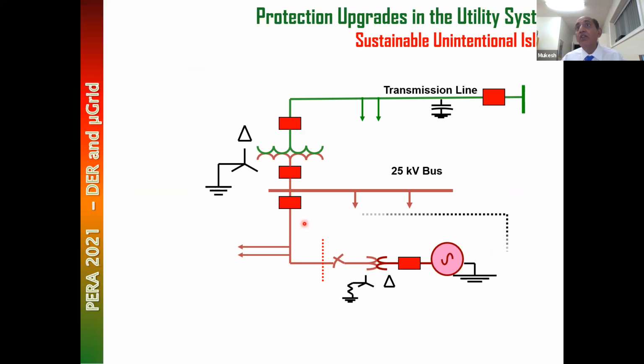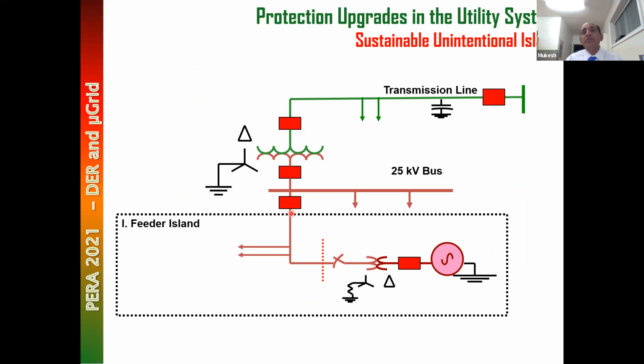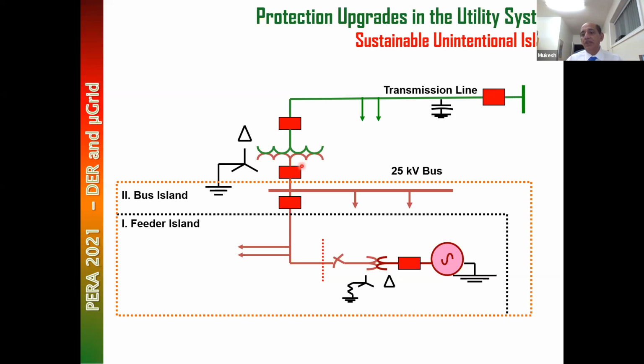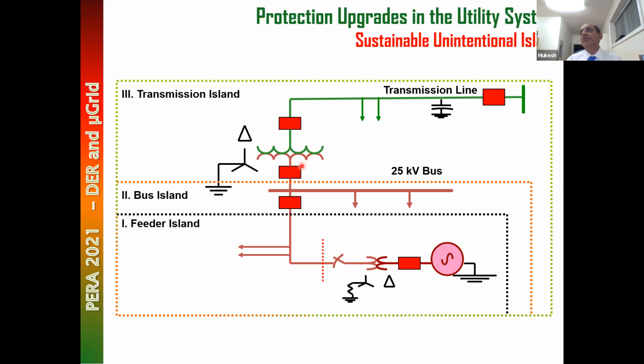So what it means is you can form a microgrid, which we call a feeder island, if this breaker opens. You can form a bus island if this breaker opens. You can form a transmission island if this breaker opens. Basically, you can form three types of microgrid: at feeder level, at bus level, or at transmission level. If this feeder load is at its minimum, you take historical data. What we do is take 25 years of historical data, and the minimum load in 25 years happens to be twice the generation.